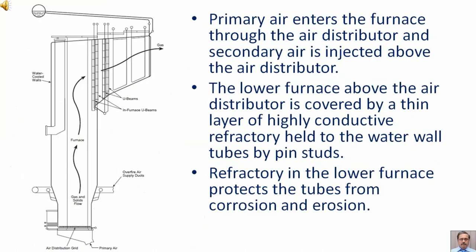Primary air enters the furnace through the air distributor and secondary air is injected above the air distributor. The lower furnace above the air distributor is covered by a thin layer of highly conductive refractory held to the water wall tubes by pin studs. Refractory in the lower furnace protects the tubes from corrosion and erosion.